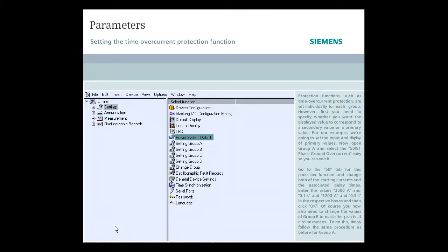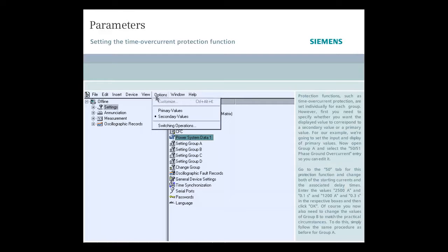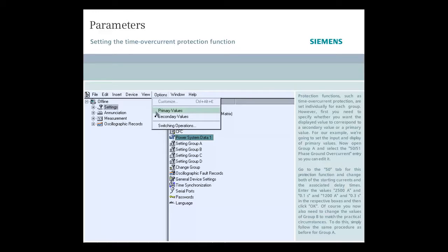Protection functions such as time over current protection are set individually for each group. However, first you need to specify whether you want the displayed value to correspond to a secondary value or a primary value. For our example, we're going to set the input and display of primary values.